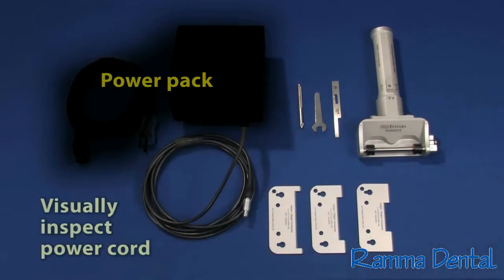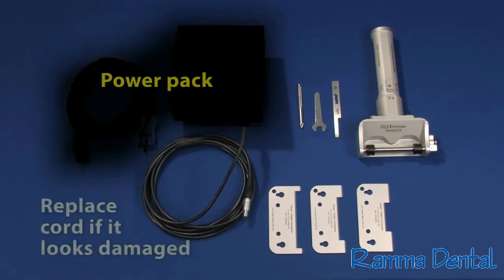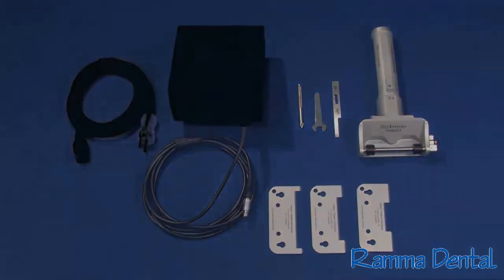Visually inspect the dermatome's power cord for signs of damage. That may include cracks or discoloration of the cable jacket, exposed conductors, or distortion of the cord or connector. If damage is observed, do not use the dermatome. Contact Integra Customer Service to order a replacement cord.